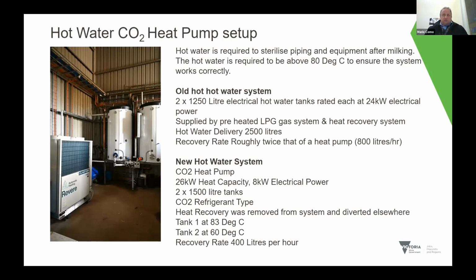And the new system we installed, which you see on the side there, is a CO2 heat pump system. It's a 26 kilowatt heat capacity, 8 kilowatt electrical power rated. We put in 2 by 1,500 litre tanks. Refrigerant type is CO2. Heat recovery was removed from the system and diverted elsewhere, and we will explain why we did that. We call the hot water tank, 83 degrees, tank 1, and the warm water tank, 60 degrees, tank 2. The recovery rate is 400 litres per hour.